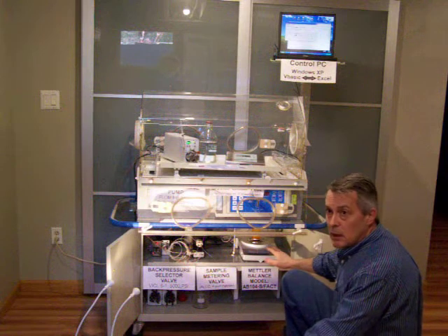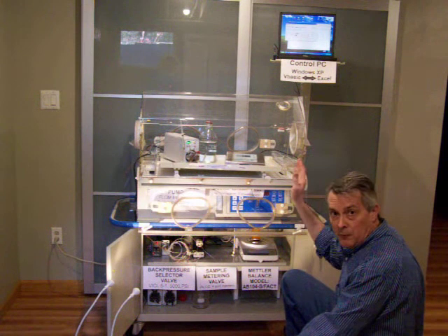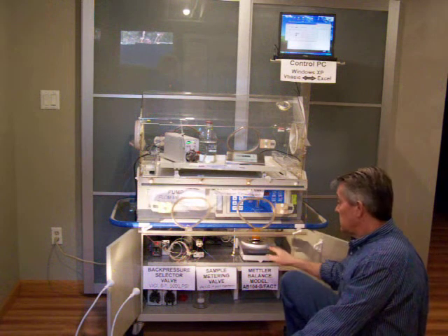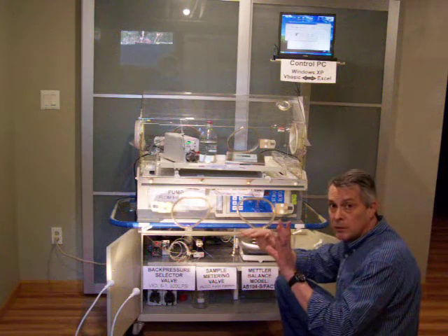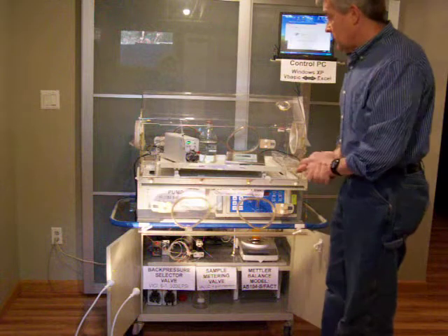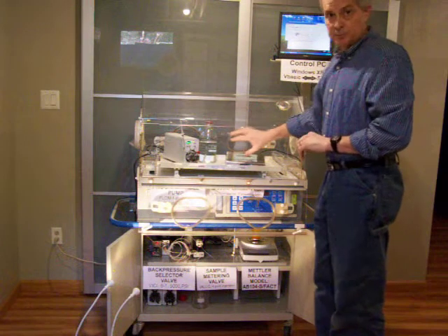And then after a given period of time, as defined by the Excel file, which automates the process, the mass is read again. Delta mass over delta time equals flow rate, because the density of any given fluid at a given temperature is known.